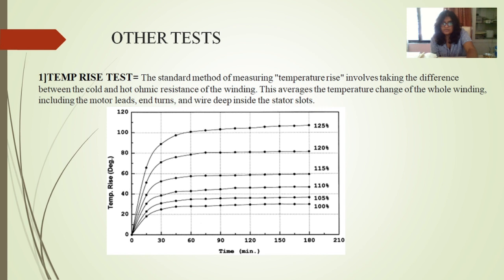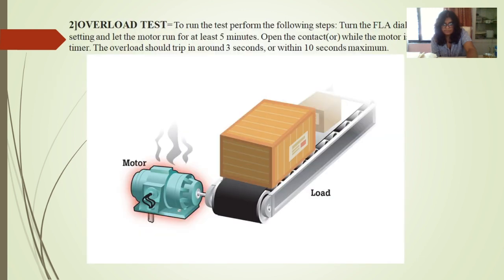The other test comprises of, as we earlier discussed, the temperature rise test. The standard method of measuring temperature rise involves taking the difference between the cold and the hot ohmic resistance of the winding. This averages the temperature change of the whole winding, including the motor leads and end turns and wire deep inside the stator slots. This is a chart for your reference given below in the figure.